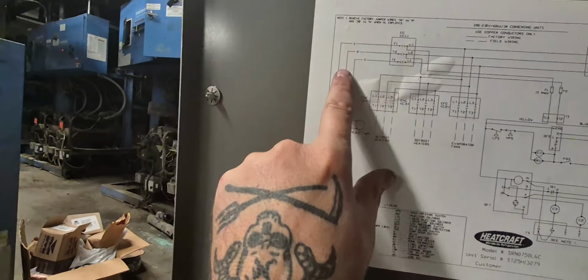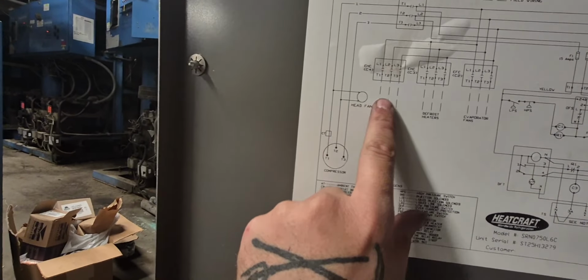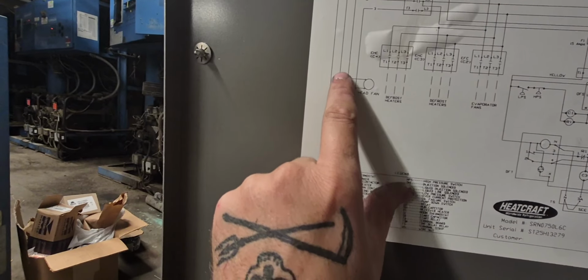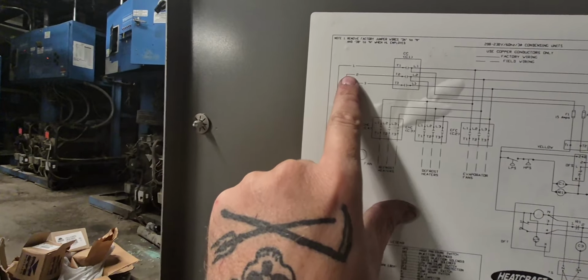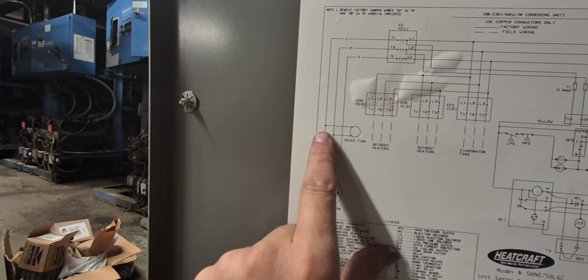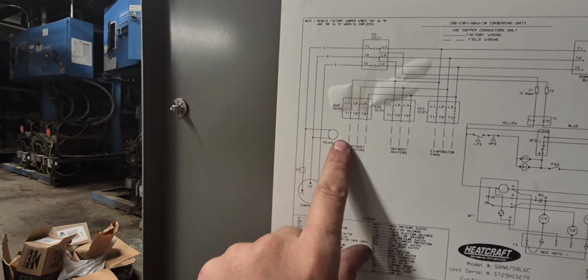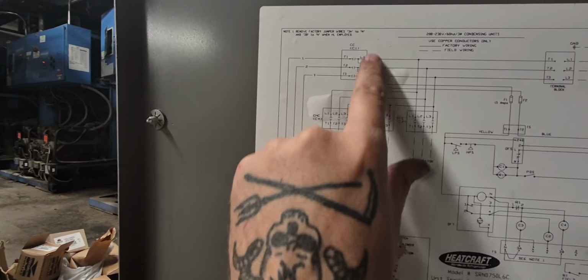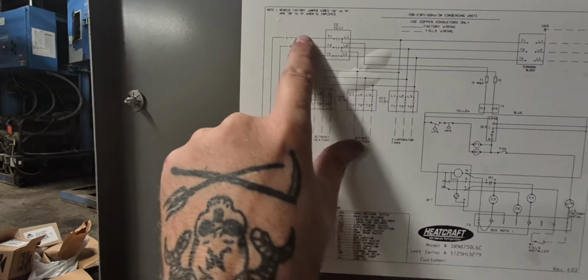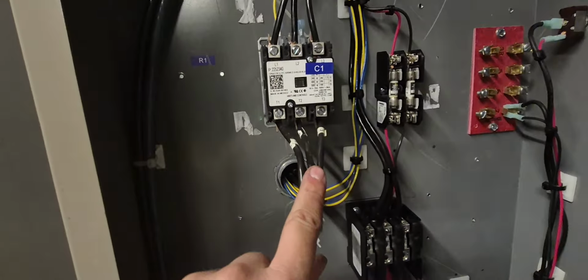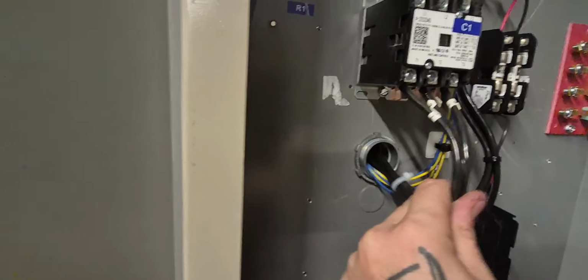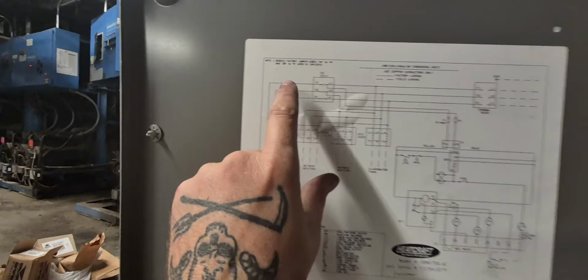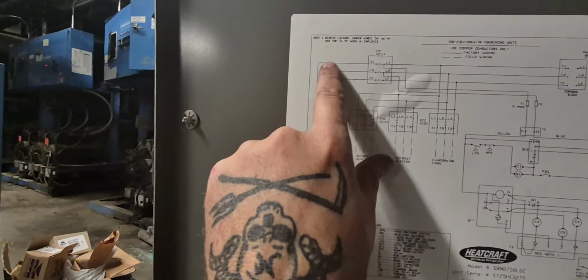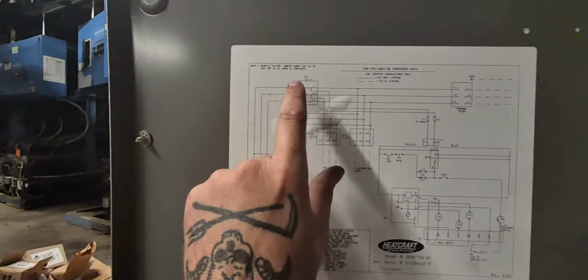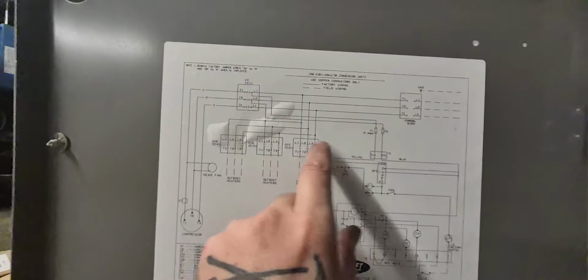And then if we follow that down, you can see it comes down. We've got our head fan right here, which comes off of L1 and L2. So L1, L2 are powering our head fan, and you can see that's after that compressor contactor. So after the compressor contactor it goes through here, which I'll show you in a second. And also understand all of these lines on paper represent real lines inside of here.